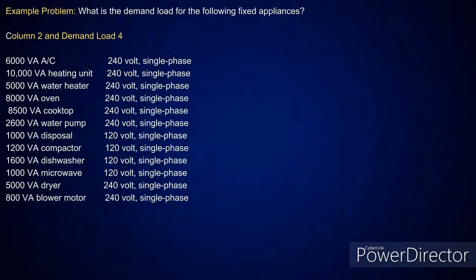So the only other load that's left is the largest between the heating and AC. Okay? Right. And that's called a non-coincident load in 220.60. We'll look at that after we finish this. But everything else that's left goes where? Here in the fixed appliance. I don't care if it's 240, 120, whatever.